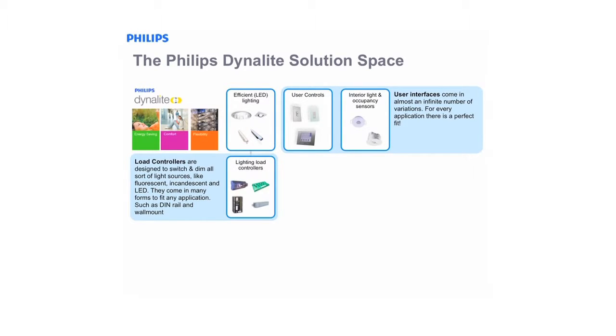User interfaces, allowing end users to interact with the lighting control system. Occupants of an area can use one of the lighting control panels, putting the system into a different mode. Passively, motion sensors can be used to detect if an area is occupied while measuring the naturally available light. By combining this information together, the system can select the right level of artificial light automatically that will be comfortable for the occupant while being as energy efficient as possible.